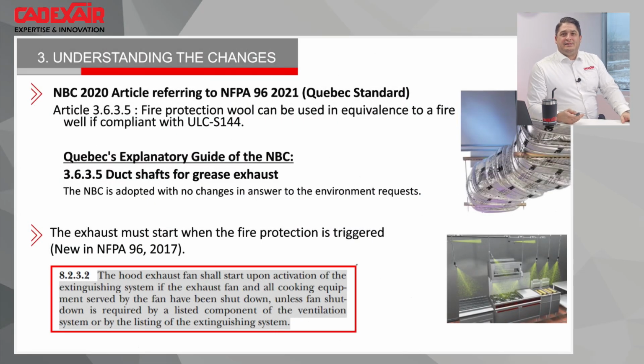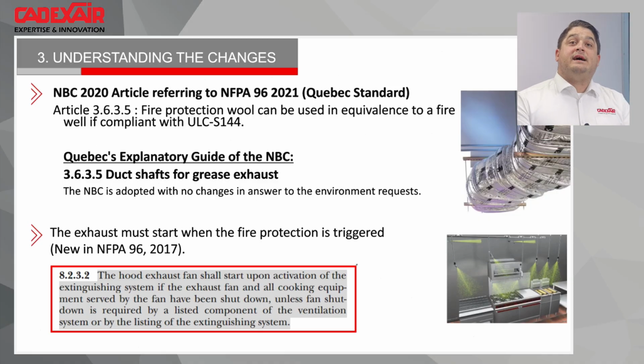This one is a bit more for Quebec about the new change. I think it was approved all around Canada, but sometimes in Quebec we're a bit strange. So now it has been listed inside of the NBC, and even in the differential booklet, the explanatory guide on the NBC from Quebec, that now we'll be allowed to use the fire barrier, fire master, or any ceramic wool that has been listed with ULC S144 as an equivalent of a mechanical shaft or to exhaust from the fire zone.